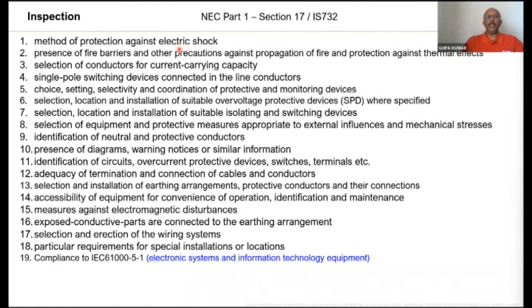As Santosh sir told, in a lot of cases, fire accidents start from loose connections. So if you test as per this particular recommendation, resistance of conductors, in case of loose contact, or sometimes the loose contacts are inside the conduit, you may not be able to physically see it. But if you do this particular test, you can very easily find out the loose contacts.